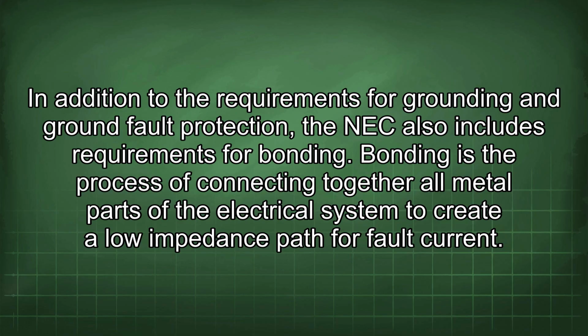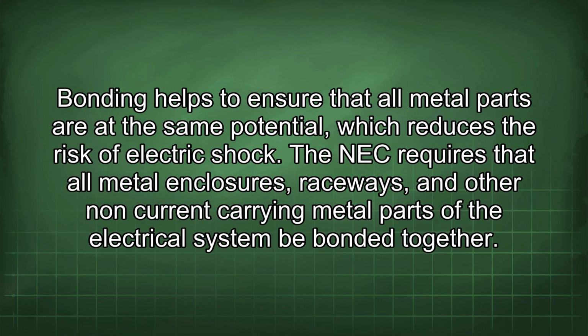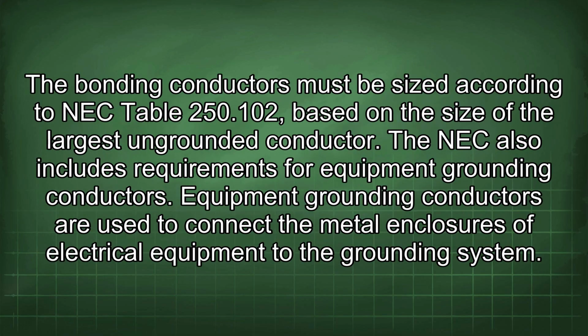In addition to the requirements for grounding and ground fault protection, the NEC also includes requirements for bonding. Bonding is the process of connecting together all metal parts of the electrical system to create a lower impedance path for fault current. Bonding helps to ensure that all metal parts are at the same potential, which reduces the risk of electric shock. The NEC requires that all metal enclosures, raceways, and other non-current carrying metal parts of the electrical system be bonded together. The bonding conductors must be sized according to NEC Table 250.102, based on the size of the largest ungrounded conductor.